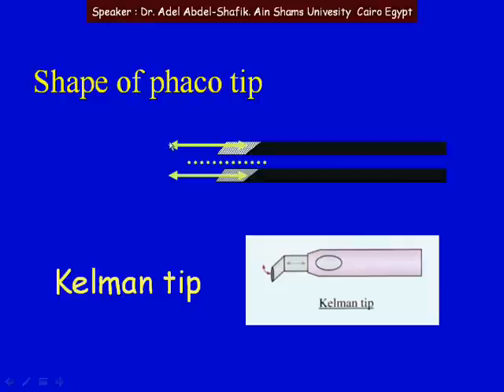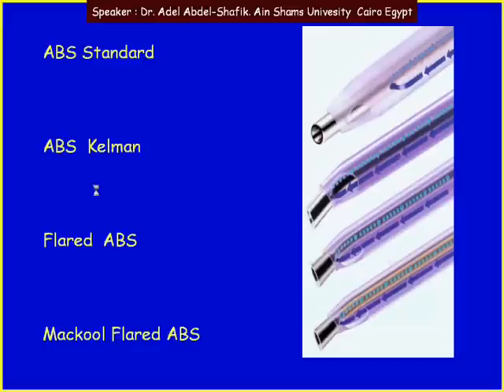We can also change the shape of the tip by using a Kelman tip. With the standard tip, the effect is only opposite the metal part, but if you bend this metal part, you get a wider surface area to achieve the phaco effect.